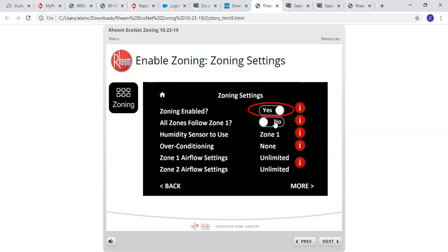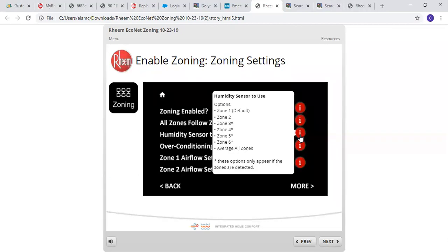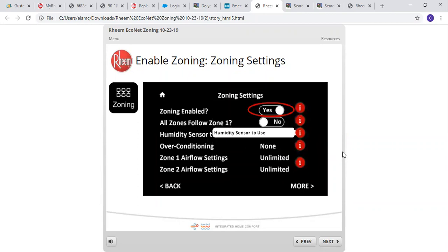So I can't think of a lot of applications where you'd want all your zones to follow Zone 1. Otherwise, there'd be no need for zoning. So your humidity sensor, your default's going to be Zone 1. That's going to be your main zone. So you can use the sensors to use Zone 2, 3, 4, 5, 6, or you can average all zones. These options only appear if the zones are detected.